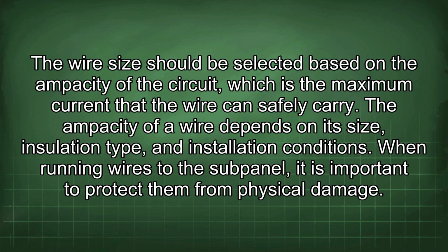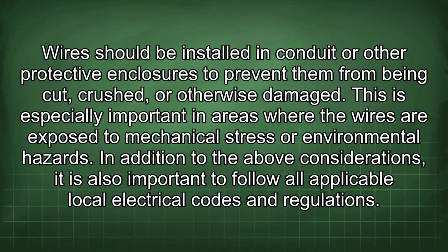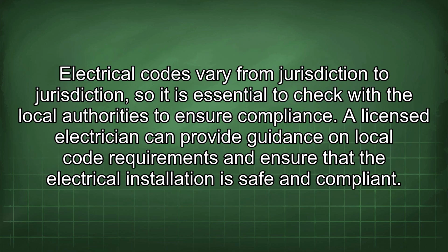When running wires to the subpanel, it is important to protect them from physical damage. Wires should be installed in conduit or other protective enclosures to prevent them from being cut, crushed, or otherwise damaged. This is especially important in areas where the wires are exposed to mechanical stress or environmental hazards. In addition to the above considerations, it is also important to follow all applicable local electrical codes and regulations. Electrical codes vary from jurisdiction to jurisdiction, so it is essential to check with the local authorities to ensure compliance. A licensed electrician can provide guidance on local code requirements and ensure that the electrical installation is safe and compliant.